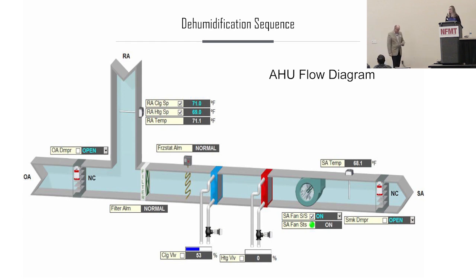So, like Bill said, humidity issues are a very common thing in Alabama. And so we usually include this slide in presentations because even if you don't have a dehumidification sequence programmed in your units, but maybe you're having humidity issues, if you have this kind of setup where you have cooling coil and then reheat, you're able to dehumidify.